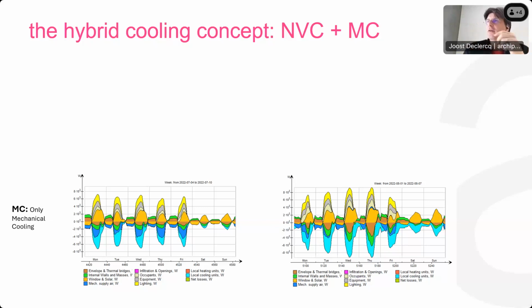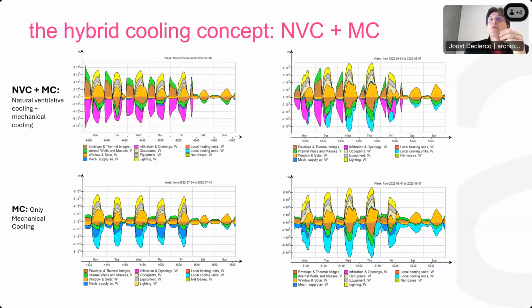And on the right, even the hottest week in our model, the first week of August. If we look at what happens with this hybrid cooling concept, natural ventilative cooling with mechanical cooling, you see in the purple parts where this ventilative cooling is extracting energy out of the building. You also see, in the dark brown parts, how the thermal mass is really activated, loading and unloading the whole time.